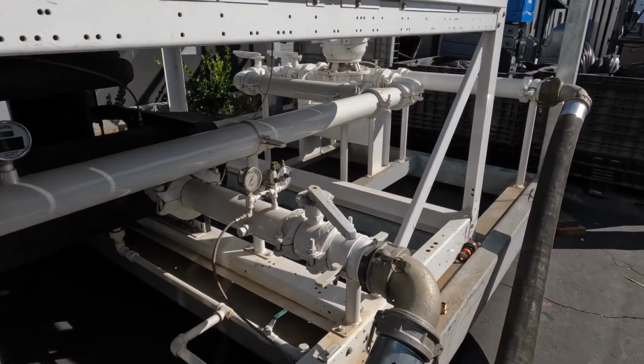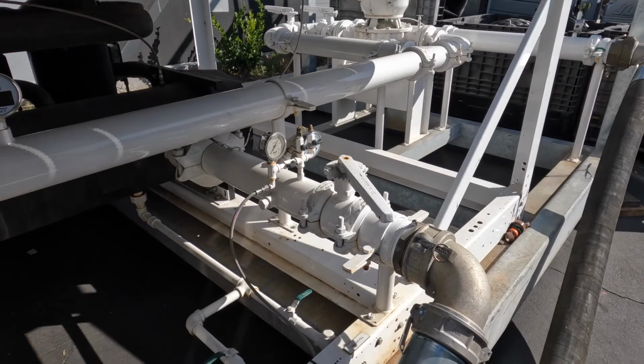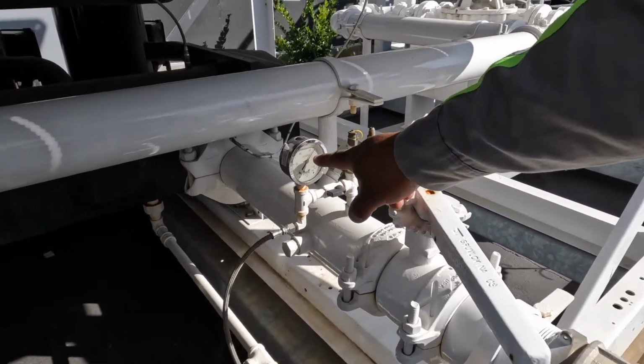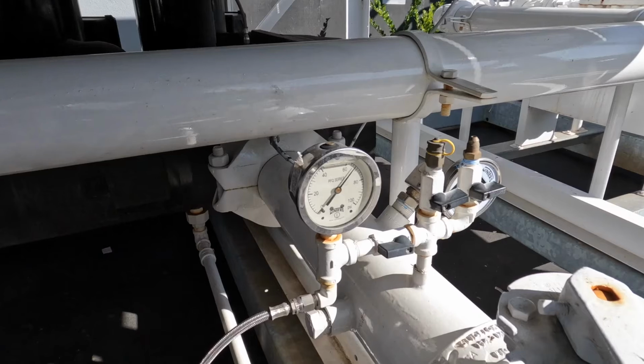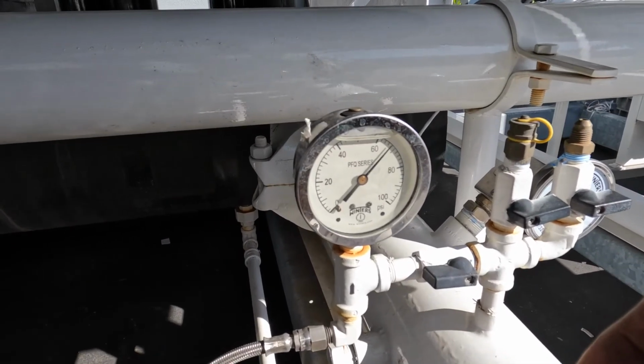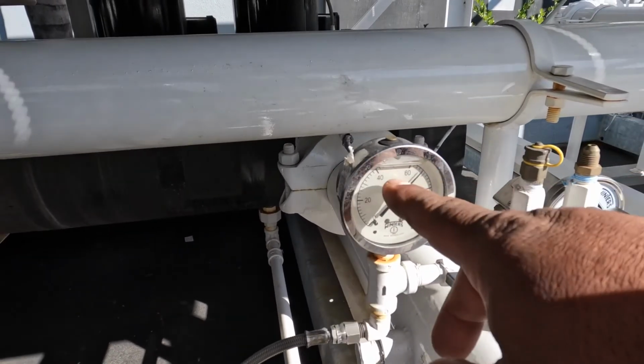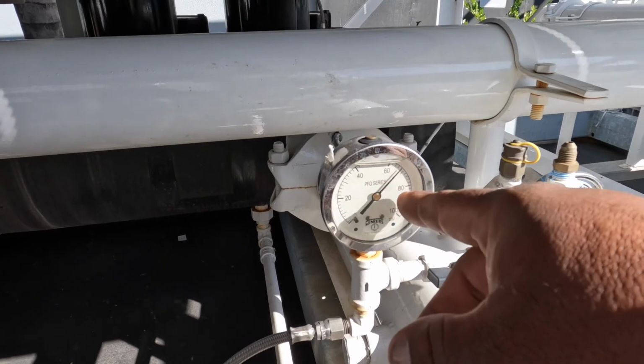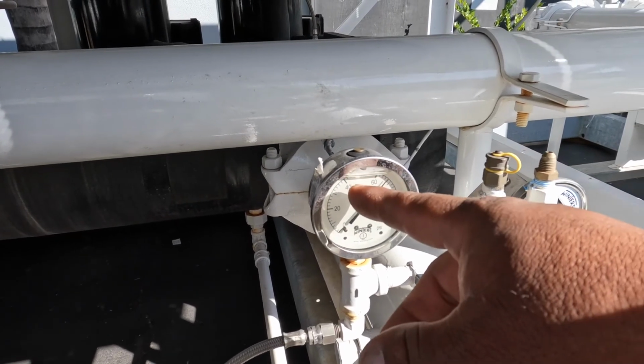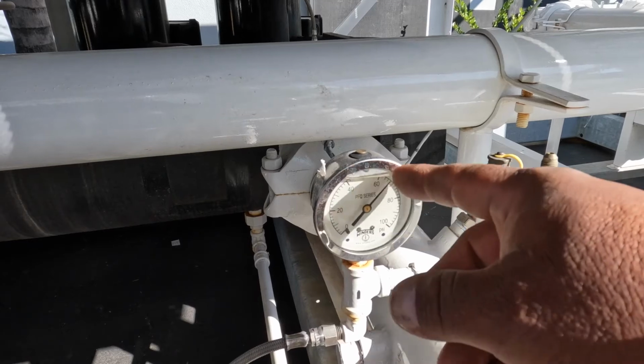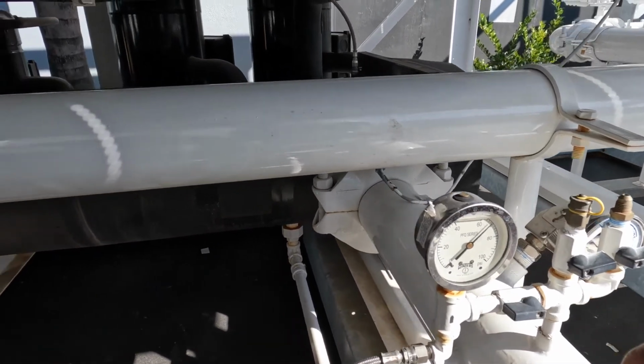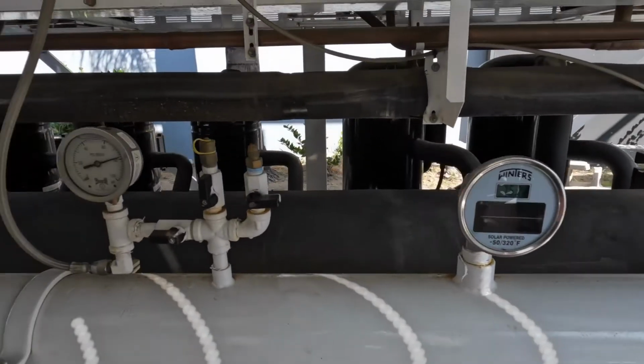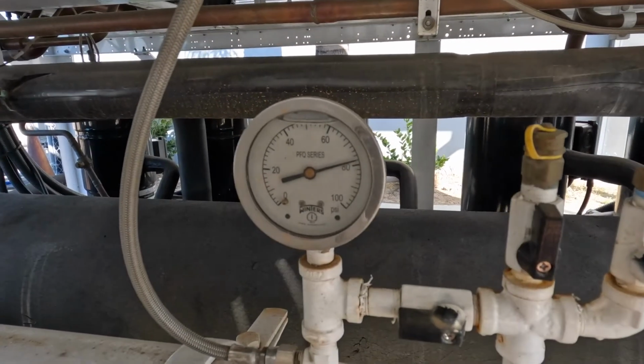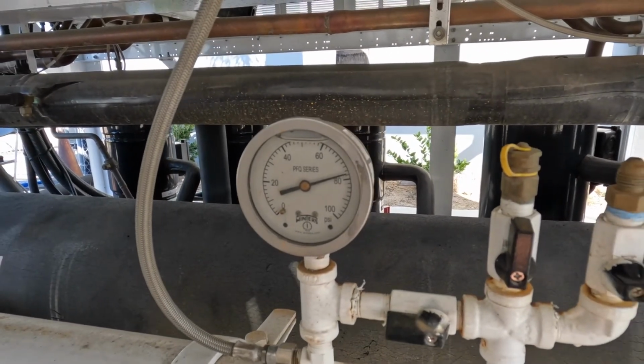Every morning before you come in and turn on the chiller, you want to make sure that the water pressure here and there are anywhere above 40 psi. If it's anywhere below 40 psi, you must add water to it, because if not, you'll start getting faults such as low suction pressure or freezing.